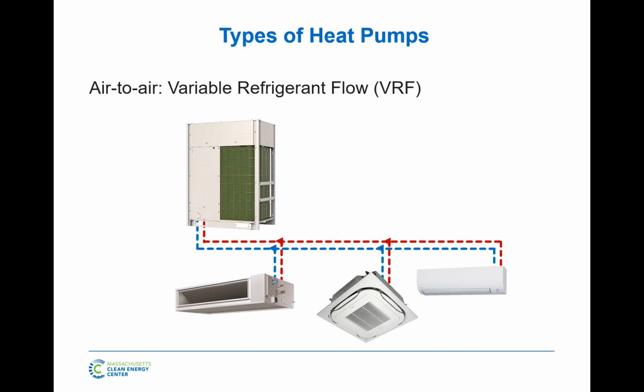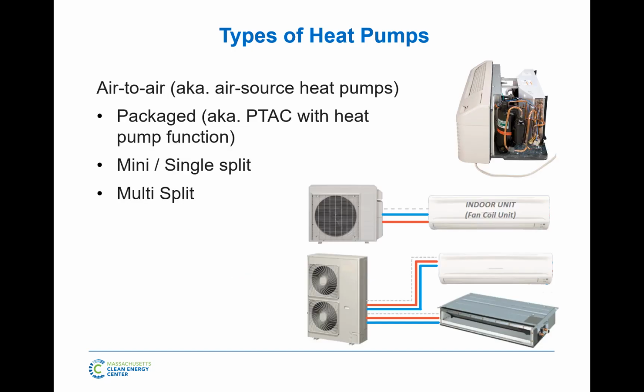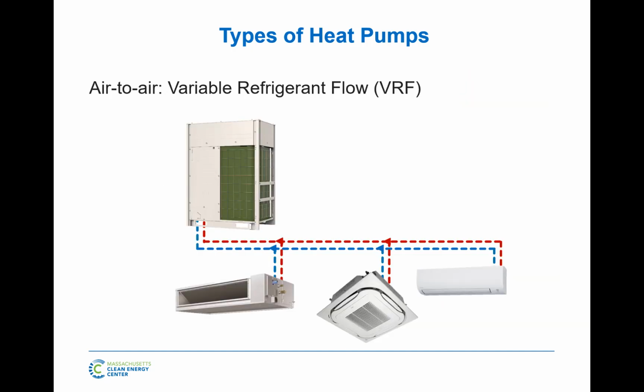Then we get to our favorites, which is the commercial versions of air source heat pump, which is VRF, or variable refrigerant flow. VRF is essentially a larger version of this mini-split, multi-split outdoor condensing unit that can connect to 3 or 10 or 30 or 60 indoor units. And you can twin them. Here's one machine. We can put 2 or 3 machines. Usually don't go beyond 3, and make them into much larger systems, 20 tons, 30 tons.